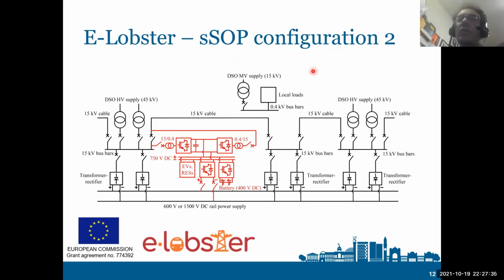A different configuration of the SOP is for a larger scale system, where we can inject and balance power between different high voltage supplies of the DSO. Here, the main role of the SOP is to balance power between two feeders and contribute to balancing the DSO network. This is a different function, since before it was mainly for local load on the low voltage network, and here it's for the DSO at the medium voltage network.